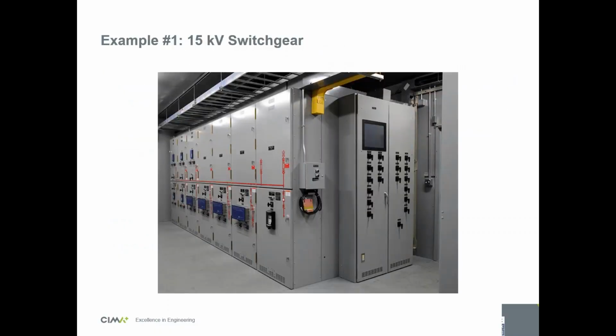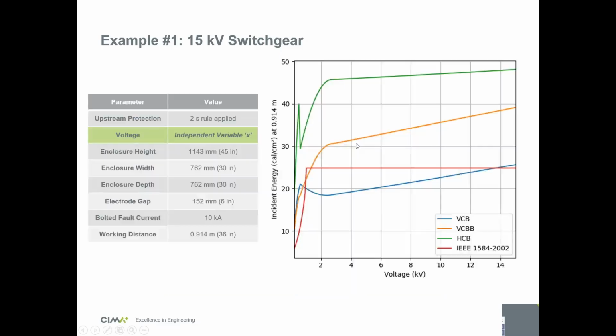So let's start with 15 kV switchgear. You have the lower section here, which has the relays, and the upper section that has the draw-out breakers, for example. Let's say your upstream protection trips in 2 seconds. That's the 2-second rule, if it's the point of connection with the utility. If you have a factory fed at 15 kV, you never know when the utility changes their protections. If they change their relay settings or their fuse type, they won't tell you. So you should always use 2 seconds on the main equipment of your facility.